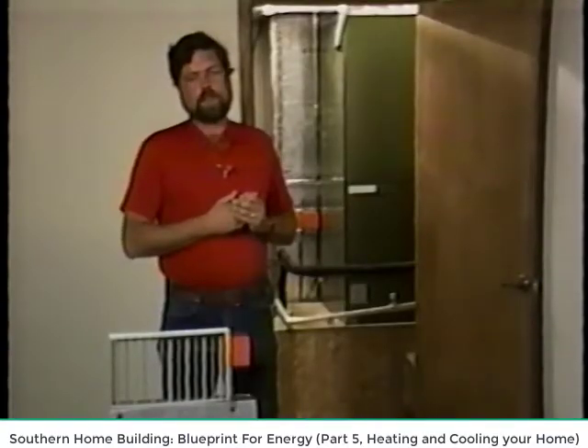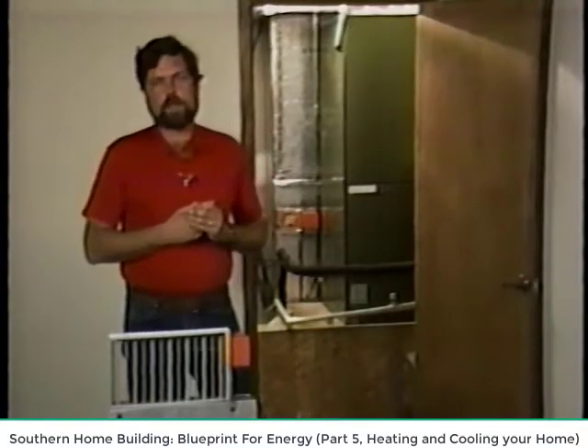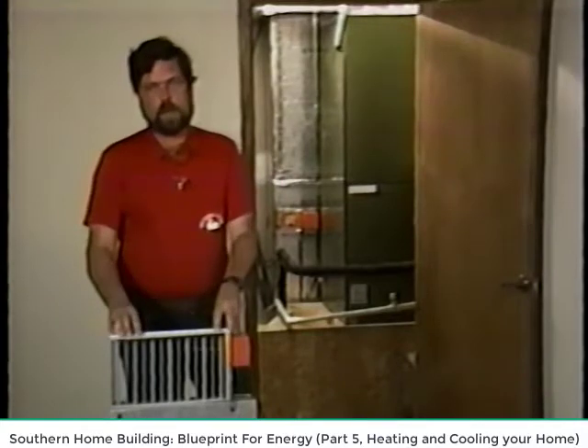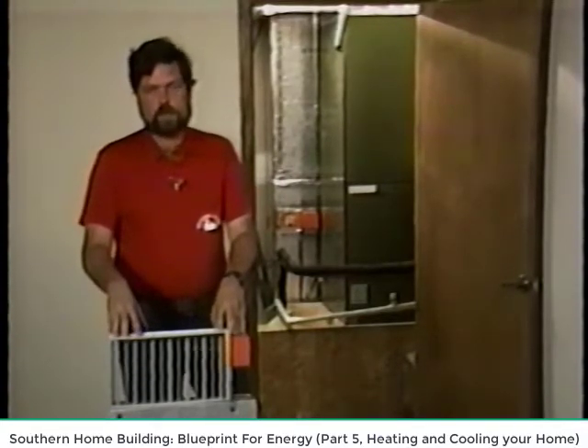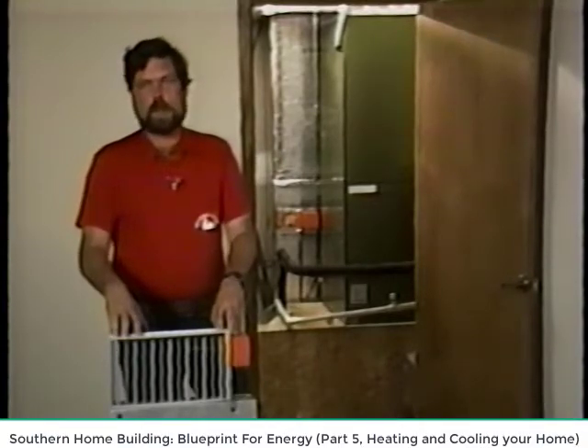There are 2 basic solutions to this distribution problem. The first one is installing 2 oversized heat pumps in your house. The first oversized heat pump upstairs to take care of the cooling load in the summer. The second oversized heat pump downstairs to take care of the heating load in the winter. This solution is expensive because it costs more to buy the equipment, it costs more to operate the equipment, it costs more to maintain the equipment, and your house is not as comfortable because it does not control humidity as well as it ought to. The second solution is to install 1 properly sized heat pump in your house in addition to using motorized dampers. These dampers will control the air to where it's needed, upstairs in the summer, downstairs in the winter.